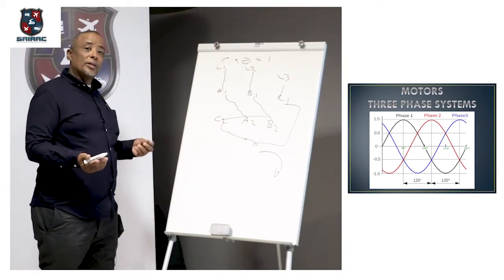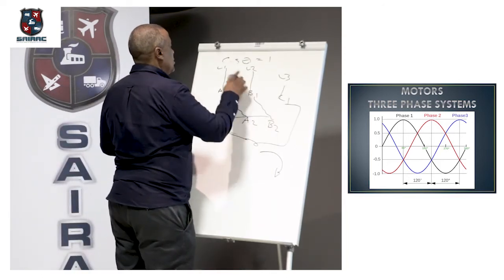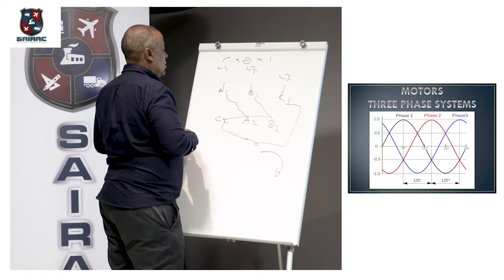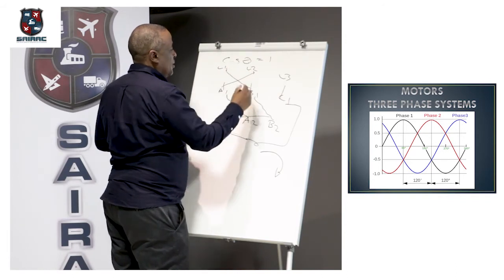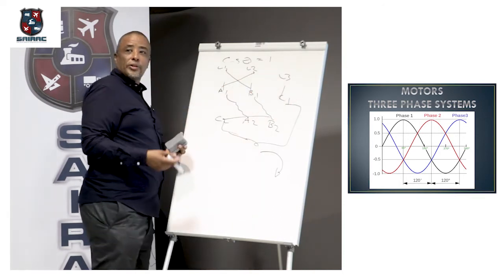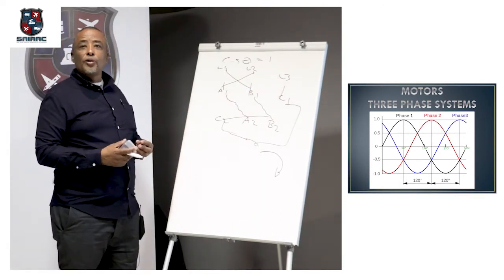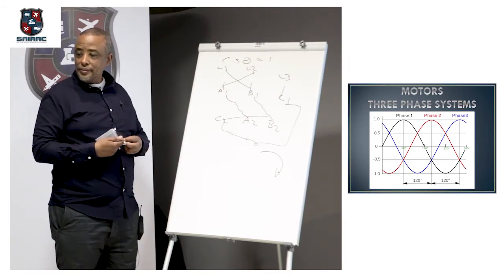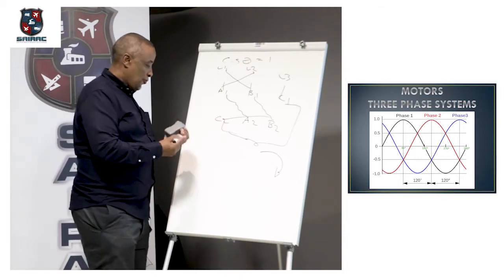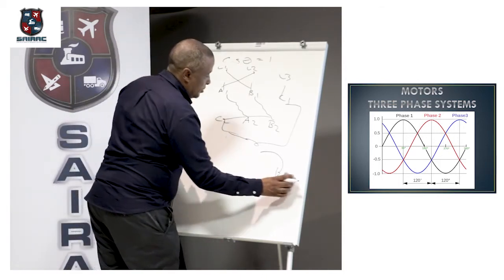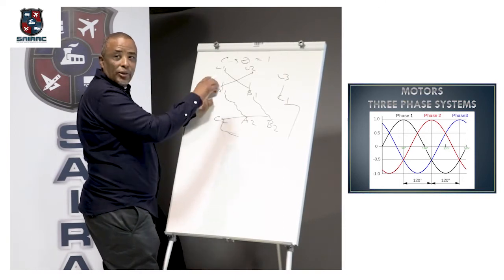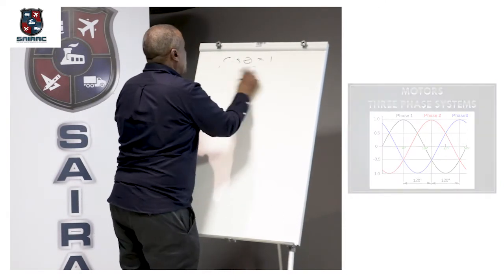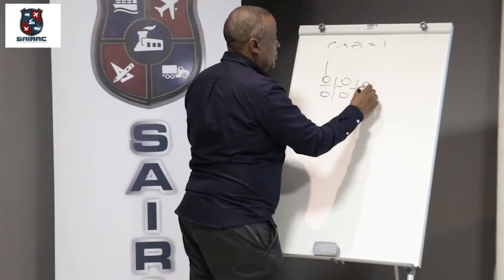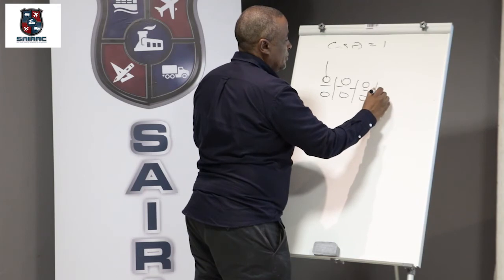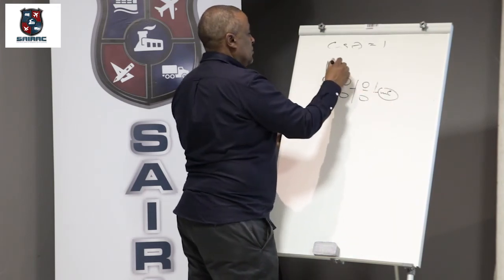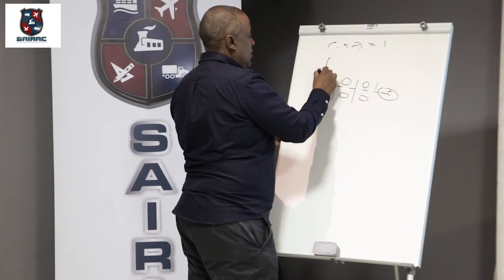If you want the motor to turn anti-clockwise, this is all we do. Either those two or those two. The motor will turn in the opposite direction. Okay, you've heard of a forward reverse starter? Okay, two contactors. One will be forward. Okay, instead of physically doing it, you'll use a starter, a forward reverse starter. Okay, yeah, that's right.